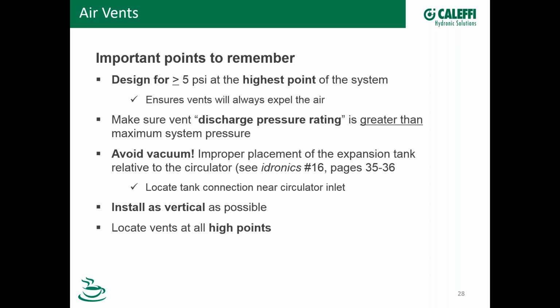And again, locate the vents at all your high points. You may need 4, 5, 6 vents, depending on your piping. We get that question a lot. How many vents do I need? Well, how many high points do you have? That's the point. And be sure to locate them for serviceability. It's very possible that over time you can get some debris or buildup in that little needle valve. It's a small orifice, and you may have to take it apart and clean it. And by the way, the vents are easily cleaned. You can unscrew the top, take them apart, clean them out, put them back together. They'll be as good as new. So if one starts to weep or drip, that doesn't mean you have to replace it. Probably just needs a good cleaning.